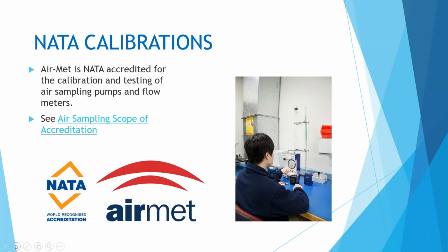AirMet Scientific is now NATA accredited to ISO IEC 17025 for flow meter and air sampling pump calibrations. So with this accreditation, we can provide NATA endorsed calibration for flow meters such as the new SKC Checkmate that Debbie's just talked about, also Defenders, dry cals, rotameters or any other flow meters you may be using against the primary standard. So our accreditation covers the range of 200 mils a minute to 5 litres a minute and is for air. So we test at 5 different points across the range of the device, and this service is carried out in our Melbourne Calibration Laboratory.